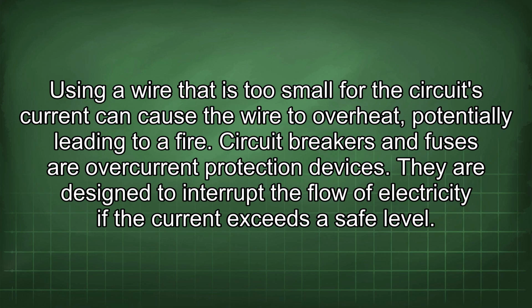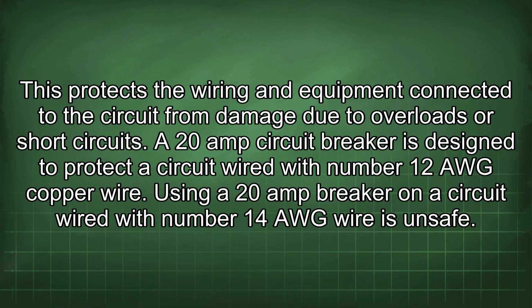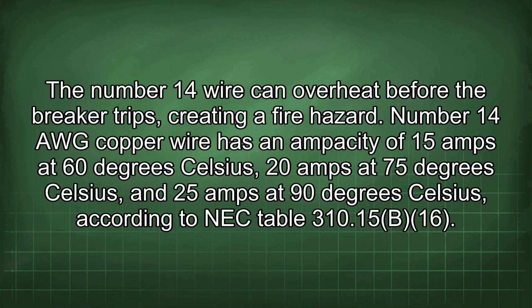leading to a fire. Circuit breakers and fuses are overcurrent protection devices. They are designed to interrupt the flow of electricity if the current exceeds a safe level. This protects the wiring and equipment connected to the circuit from damage due to overload or short circuits. A 20 amp circuit breaker is designed to protect a circuit wired with number 12 AWG copper wire. Using a 20 amp breaker on a circuit wired with number 14 AWG wire is unsafe. The number 14 wire can overheat before the breaker trips, creating a fire hazard.